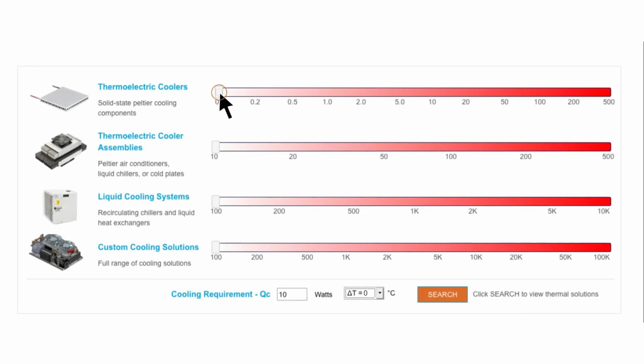And you mentioned delta T versus pumping power. It's basically an inverse relationship, right? So if you want very little temperature differential, it can handle a very high heat load. If you want a high temperature differential, it can't really handle a very high heat load. That's right, almost opposite. One of the things here is I've been doing thermal engineering for a very long time, and a lot of air cooling and liquid cooling applications make sense, you can do the math. When it comes to TECs, the math gets really complicated really quickly. One of the ways I recommend engineers go is to check out Laird Thermal's website, it's one of the best websites I've seen.